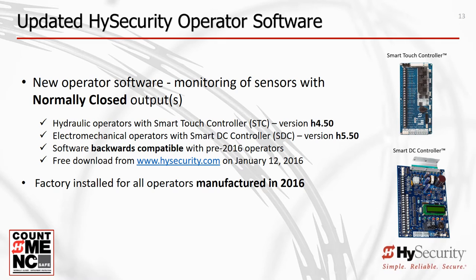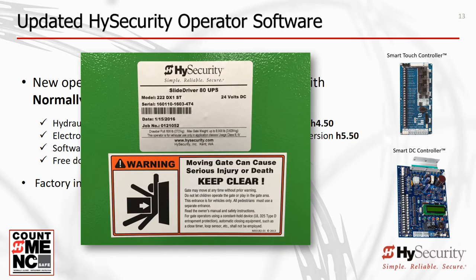The new UL325 2016 SmartTouch hydraulic software version is H4.50 or higher, and the new UL325 2016 SmartDC electromechanical software version is H5.50 or higher. Software updates are accessible on HySecurity's website. An installer can easily update any HySecurity gate operator in the field by downloading new software and using a laptop and the Start program for PCs. The operator's date of manufacture can be found on the serial number label on the outside cover and inside the chassis.